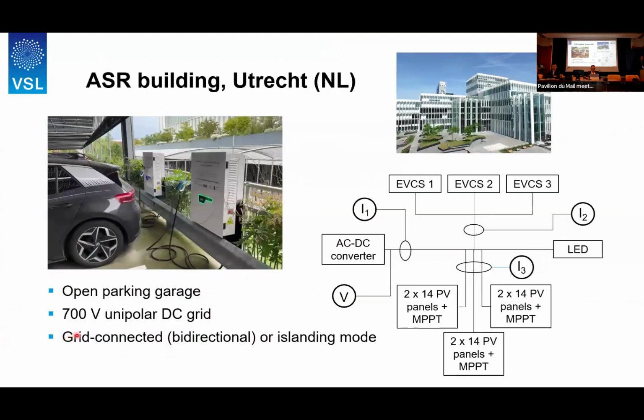So as an example, some of you might have seen this before, as an example of the type of measurements that we want to do on site. I show you results that we have measured at the DC Grids project, which is just finished. And actually, it was measured at the DC site. It's important to realize that. I will come back to that. So it was measured at the ASR building, which is an insurance company in the Netherlands. And it's an open parking garage from a 700-volt unipolar DC grid, which can be operated in islanding mode or connected to the AC grid.